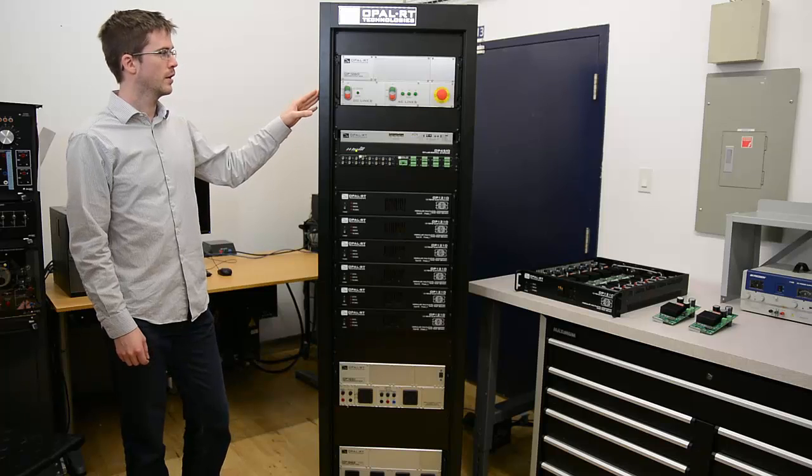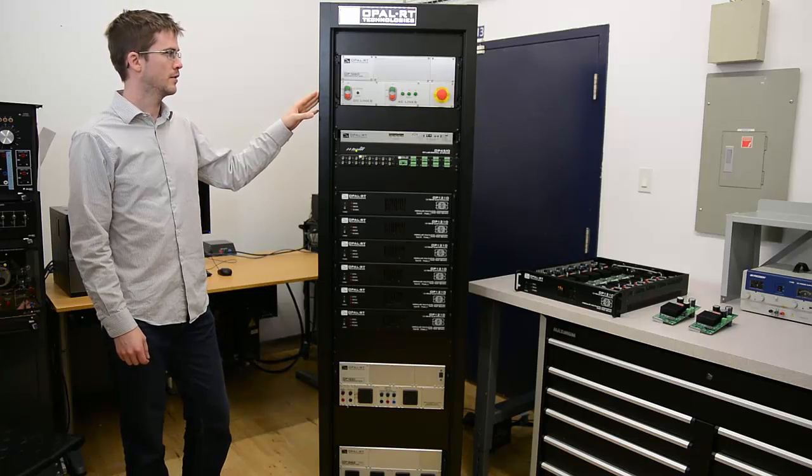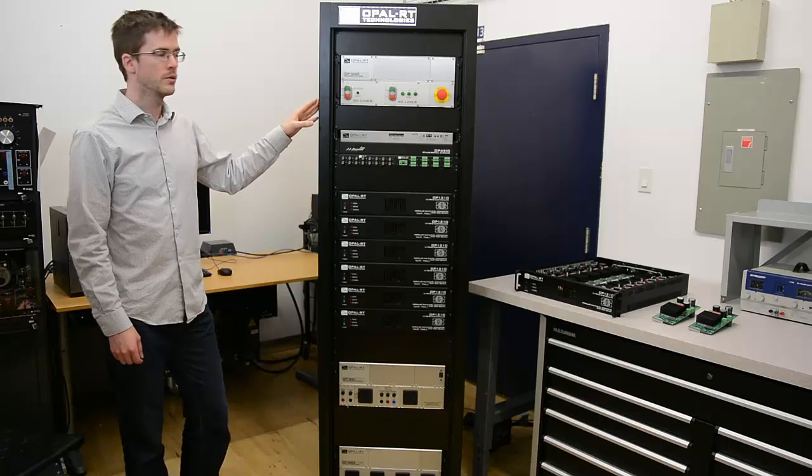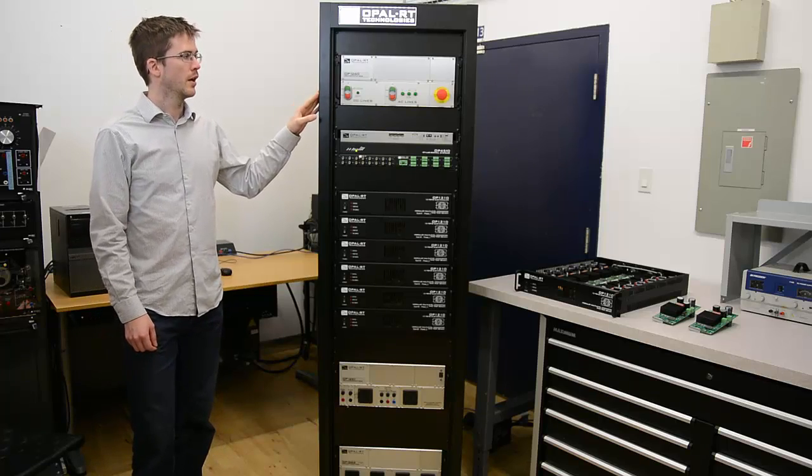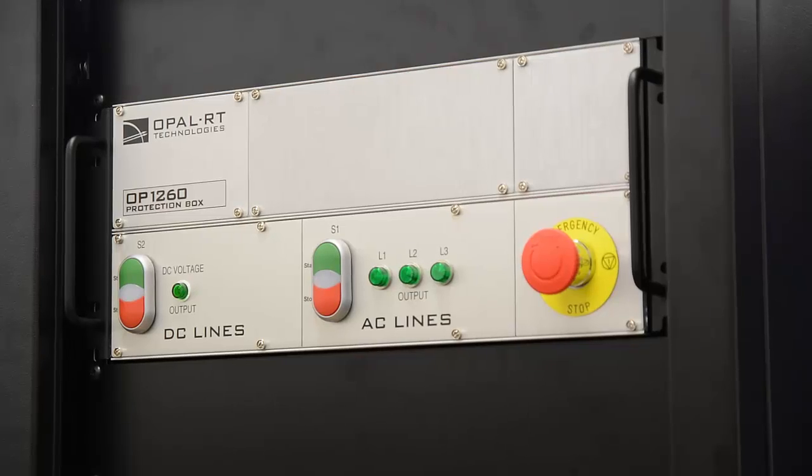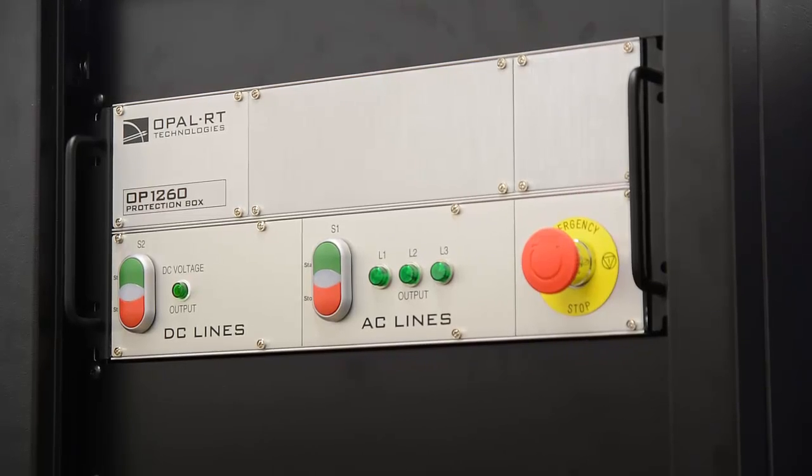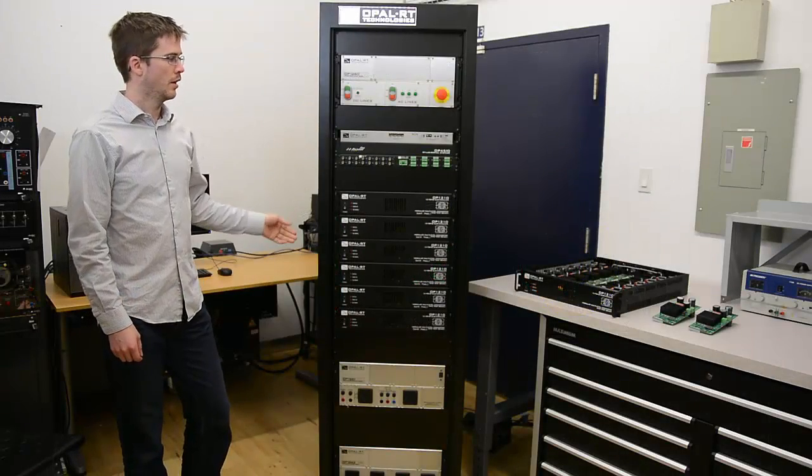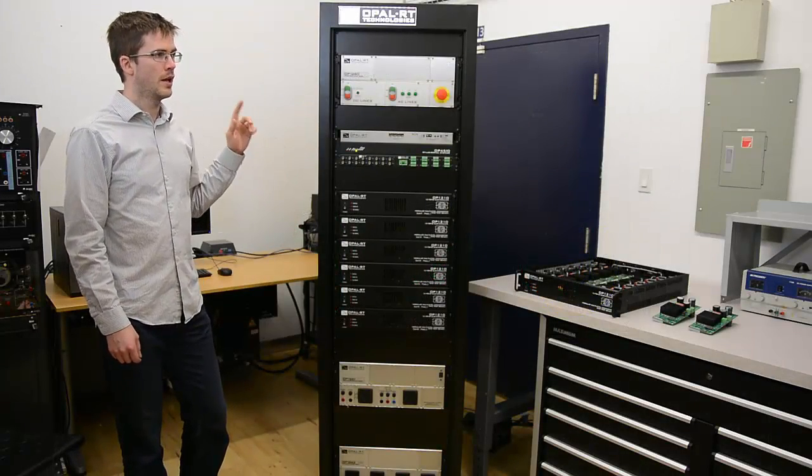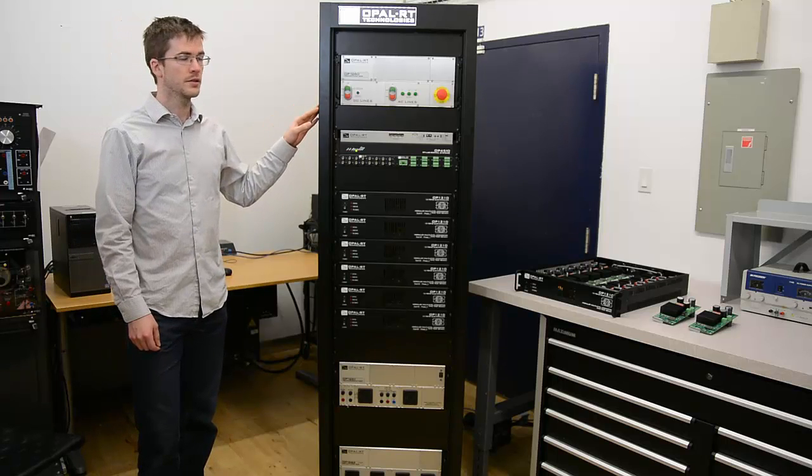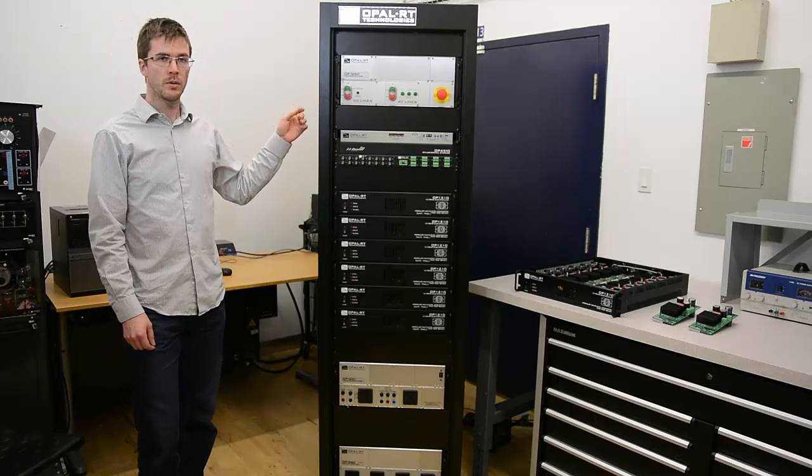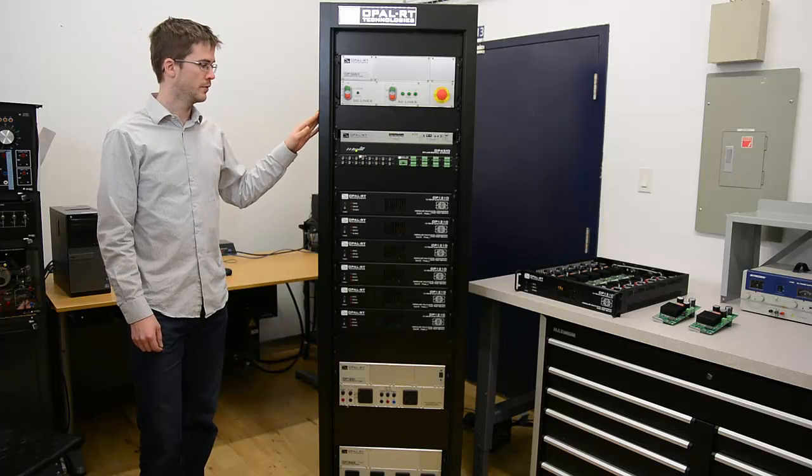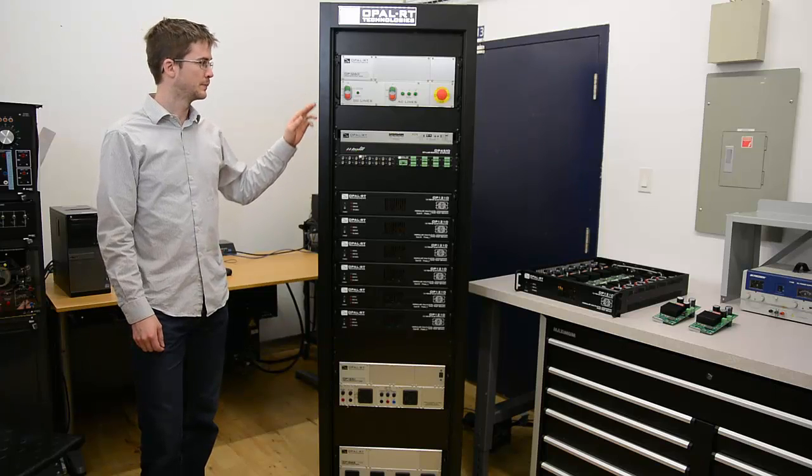The protection box is where your AC and DC lines connect to the rack. This box includes contactors and breakers to isolate the rack in case of problems, plus it includes an emergency stop to completely isolate voltages in case of emergency. In addition, it contains disconnect switches to properly isolate the rack when you want to manipulate the different modules inside.